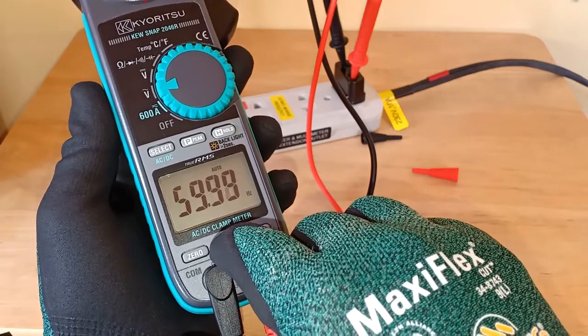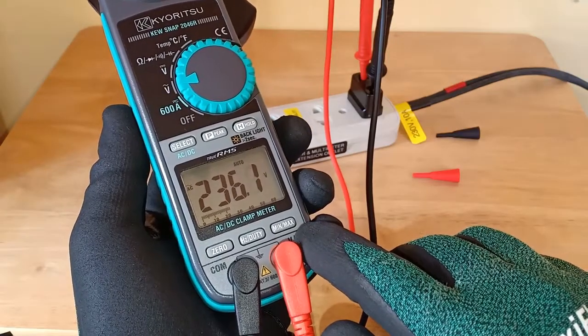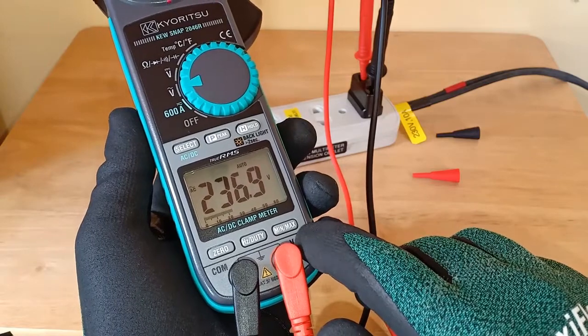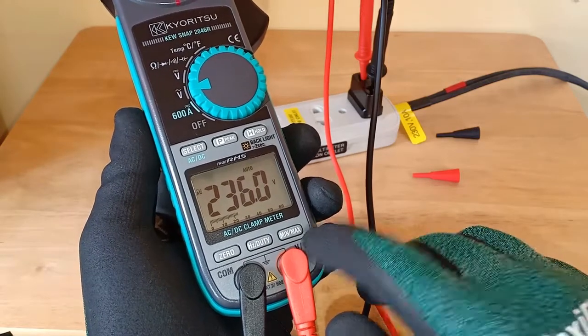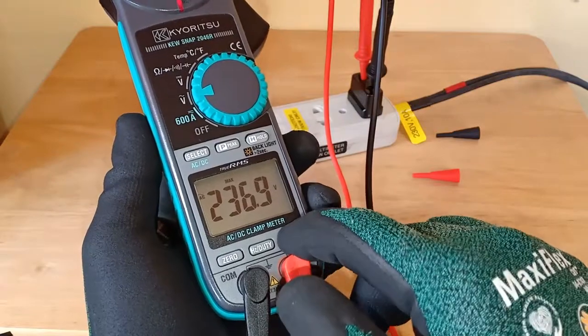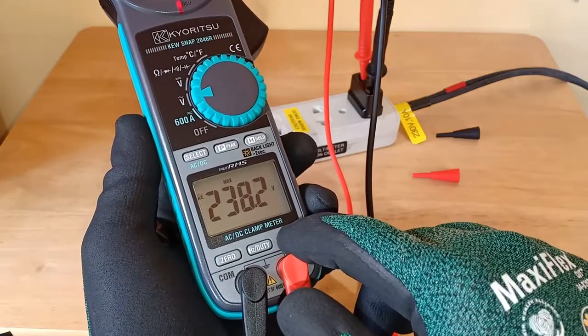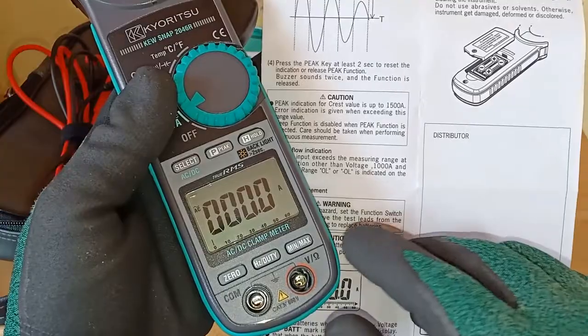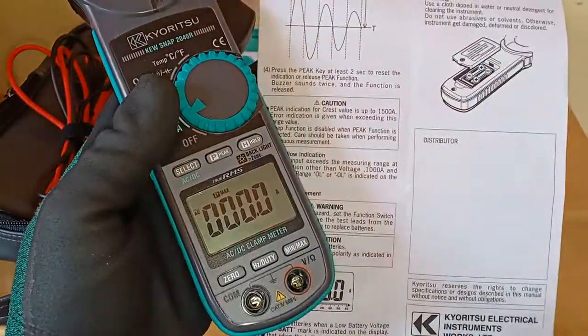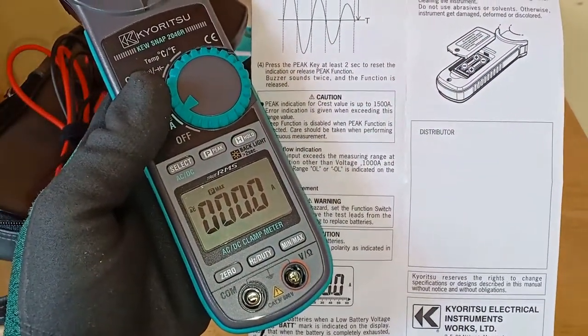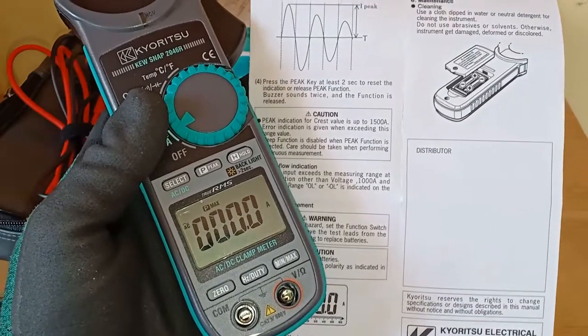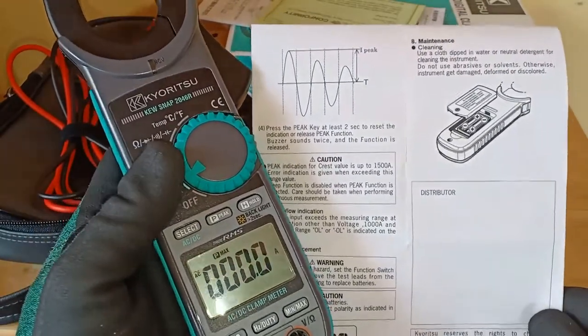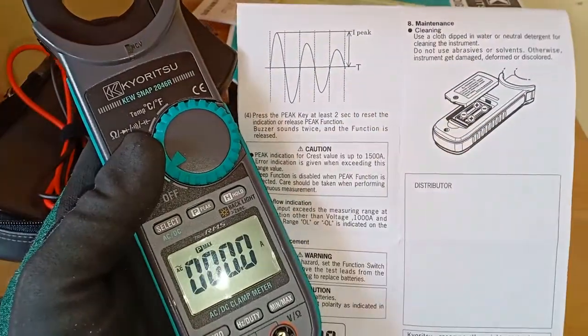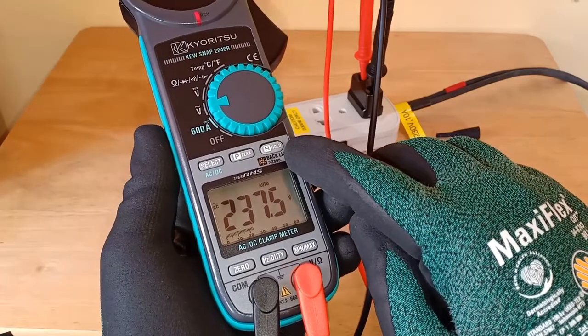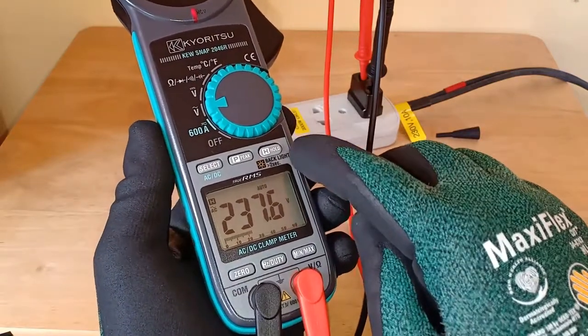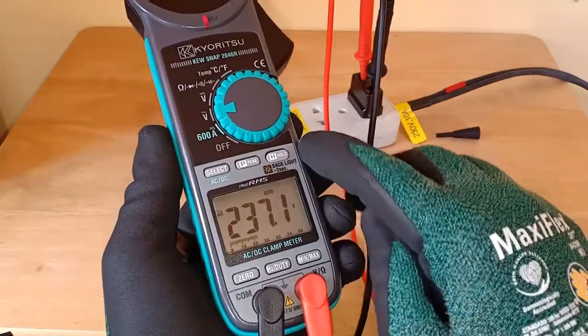and 60 Hz. The minimum and maximum button is used to capture minimum and maximum values within a monitoring period. The peak button is used to enable the peak hold function in AC current measurement. This is useful in capturing AC inrush current's peak values. The hold button will freeze the value on the screen. Data hold and backlight share the same button.